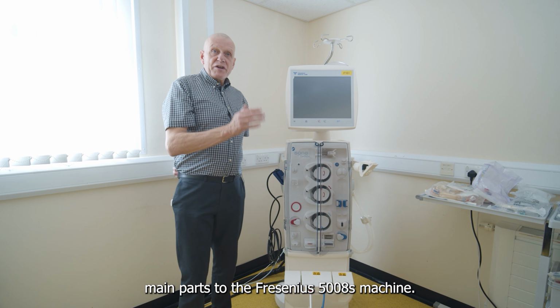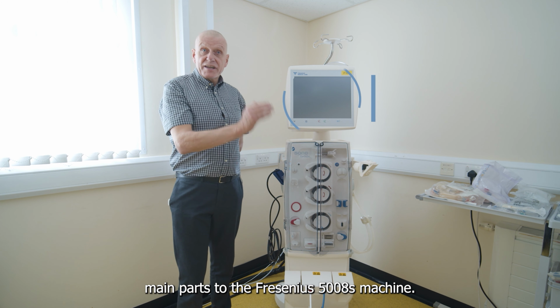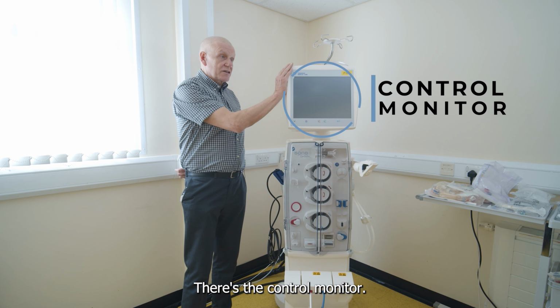So there are three main parts to the Fresenius 5008S machine. There's the control monitor. This is where you control the machine and you look at what the machine is doing, and it gives you all the readings for your blood pump speed, your venous pressure, your arterial pressure. Everything that's going on in the machine comes through this screen here. You have your on-off button here, you have your mute button here, your blood pump start and your blood pump stop.